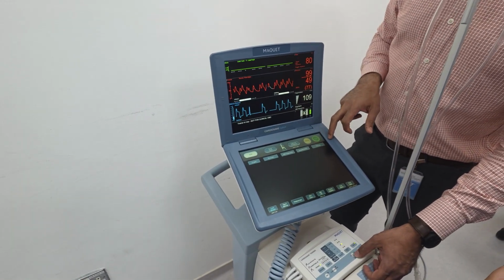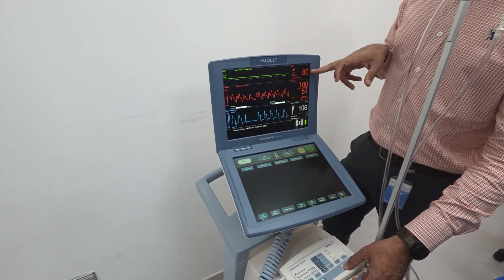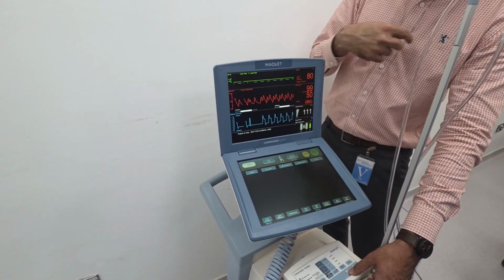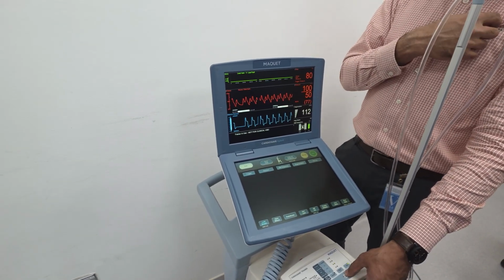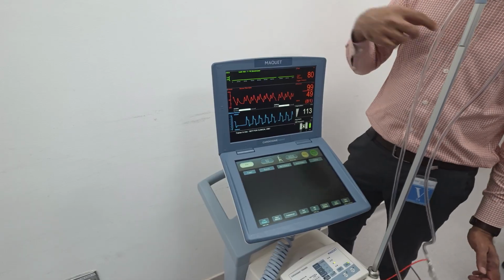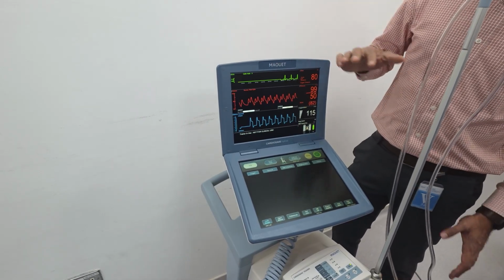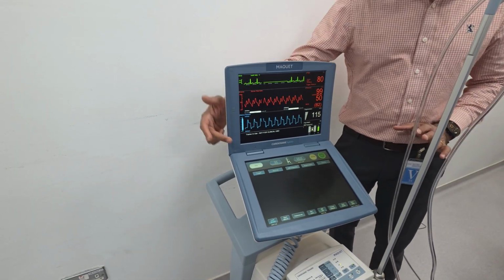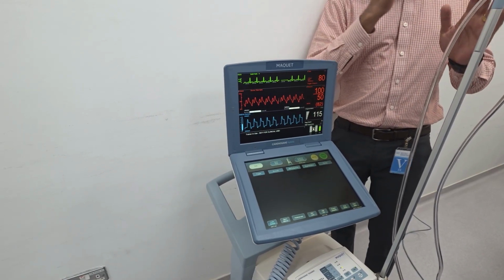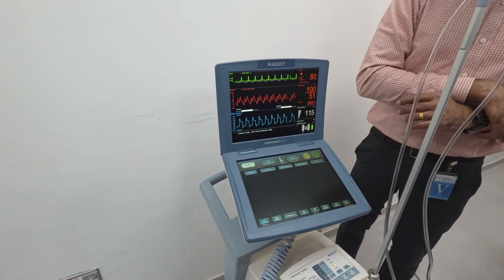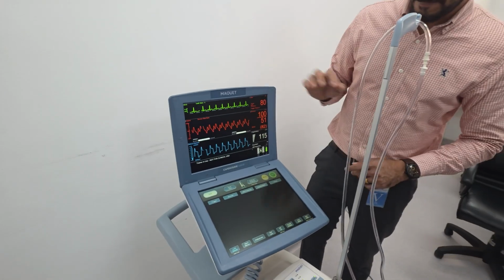Okay. So ECG is not there, right? It's still in pressure. So you know there is no ECG. You have adjusted, or one of the leads is removed. You adjust from the patient side. I can do it in my simulator. So ECG will come back. Don't worry. Again, no configuration required. Since you are in auto mode, it will check if there is a consistent ECG. It will switch back to ECG automatically. Okay.